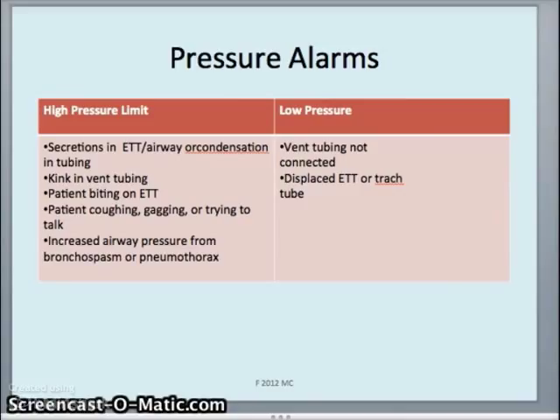So either the tubing has become disconnected from the ventilator, or the endotracheal tube or the trach tube has been displaced. Sometimes you'll walk in the room and you'll see a low pressure alarm, and there is the ET tube sitting on the patient's chest because they've either pulled it out or they've coughed it out. So that's an example of a low pressure alarm. Now, clearly, you don't intubate. We only have physicians intubate. And you're going to need to call for help if that's the case. But a lot of times things just pop off, maybe after the patient's been repositioned. So that's an example of a low pressure alarm problem that you could troubleshoot.